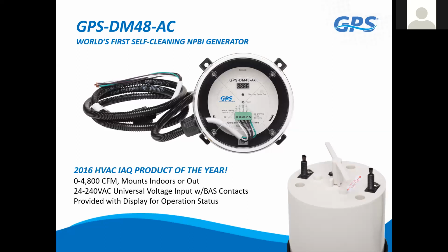So you could actually take a unit like this, put it in that duct that's feeding that one zone, and it would be the zone that the person is complaining about, because the smoke in there is not as heavy, so it's easier to treat than the person that's smoking. We don't want to help that person out. We want to help the person out that's complaining. So you put this in there and it's going to take care of that. With that, you don't have to treat the whole building. So let's say you have a 40 or 60,000 CFM central station unit that's providing heating and air to the whole space, you don't have to treat the whole space. You can just spot treat it with one of these.